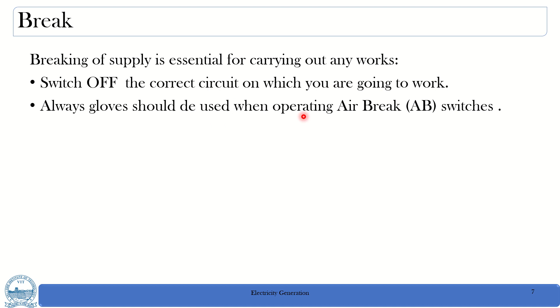This air break switch is used in the case of distribution transformers, which from the figure you can observe. This is a pole mounted transformer, which is located near everyone's place, right? You should have observed there is a long rod, and attached to the rod is a lever which acts like a switch. So this is a circuit breaker, a breaker where air is the medium, and it is operated manually by the electrician appointed dedicatedly for that purpose. And this is done by an iron rod which is insulated from the contact.